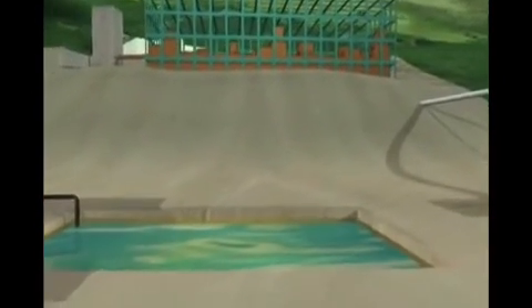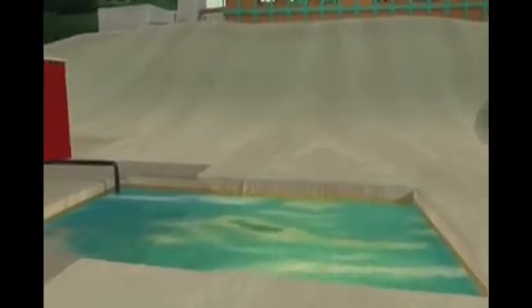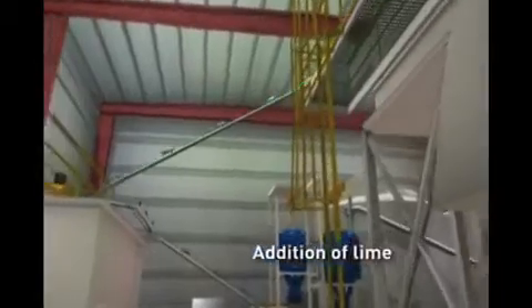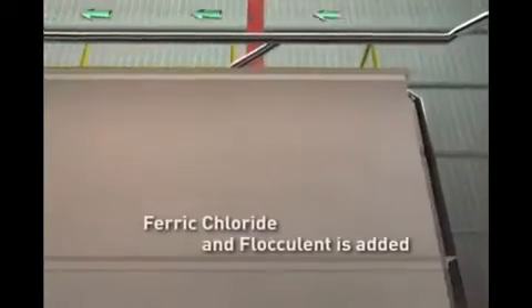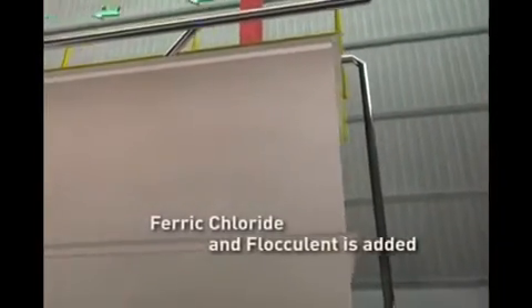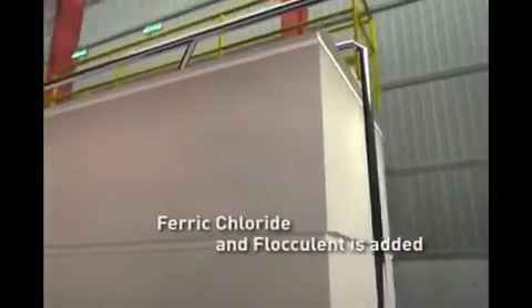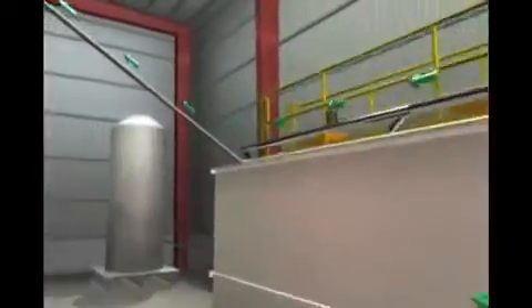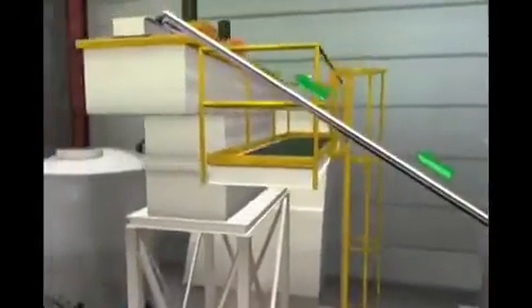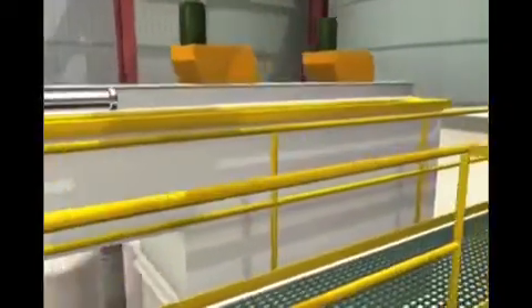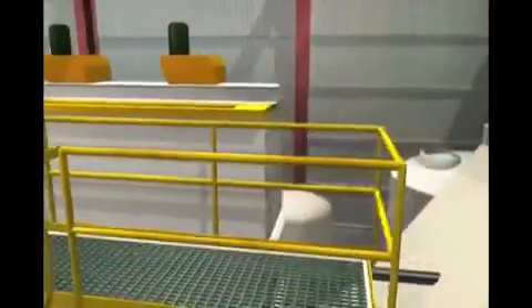Acidic mine water is directed to a main settlement pond, which feeds into the interim water treatment plant. The acidic mine water is neutralized by the addition of lime, producing a slurry with metal hydroxides as the precipitate. Next, ferric chloride is added to aid in precipitation. Flocculant is then added to promote flocculation. The slurry is passed through a thickener, producing a sludge which is about 10 to 30% solid and stored on site.